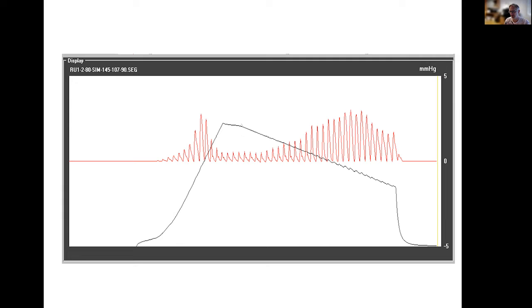The difference is that this part here is slowly controlled deflation of the device, which means that a lot of pressure pulses, which basically correspond to the heartbeats, would happen. So there are a lot of pressure pulses here because this deflation is slow. But there are also pressure pulses on the way up, meaning also on this flank here, when the pressure is increased. Just they're not that many because this happens fast, and the simulator doesn't have a lot of time to generate the pressure pulses. But basically, this pressure pulse here corresponds to this pressure pulse here. Just it's done in a fast way.